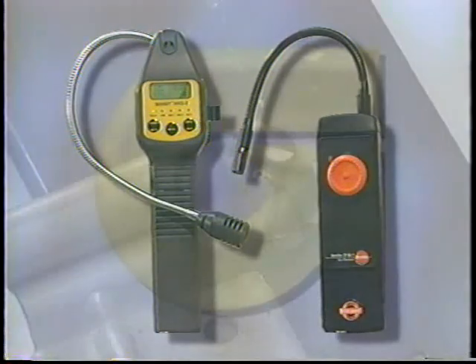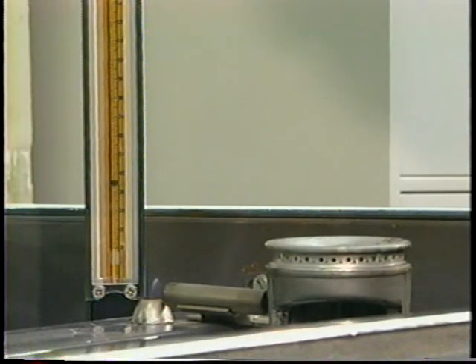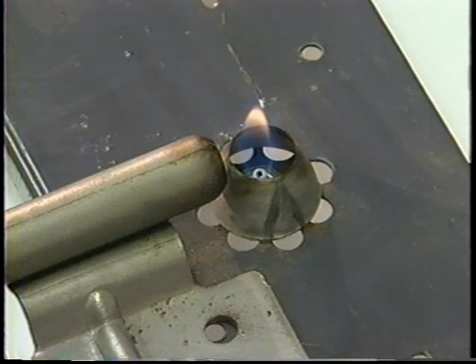According to national standards, 235 cubic centimeters of gas per hour represents the maximum allowable leakage rate for a control. Gas detectors are so sensitive that they can detect gas in amounts far below this allowable limit. Now let's perform a practical demonstration to show how small the maximum allowable leakage really is. The pilot burner on this gas range will normally burn approximately 175 BTUs per hour of natural gas, or approximately 5,000 cubic centimeters per hour.